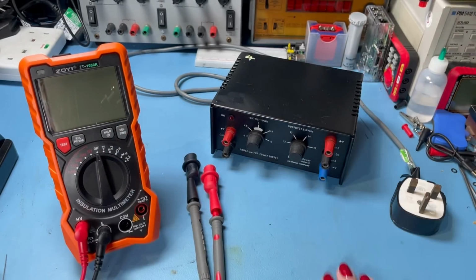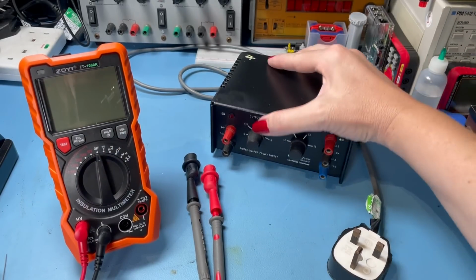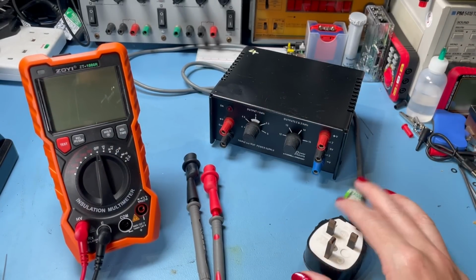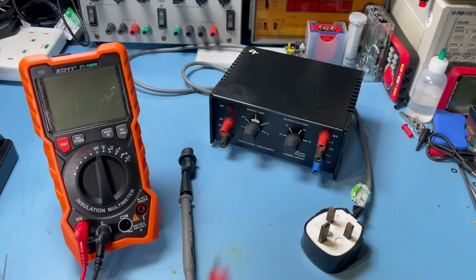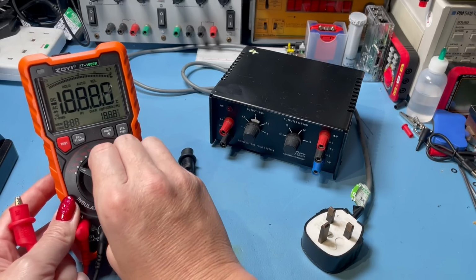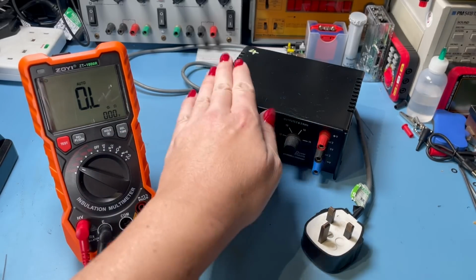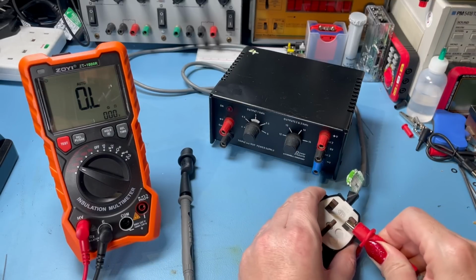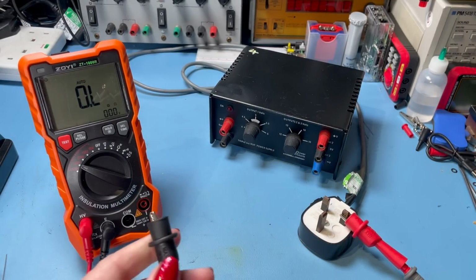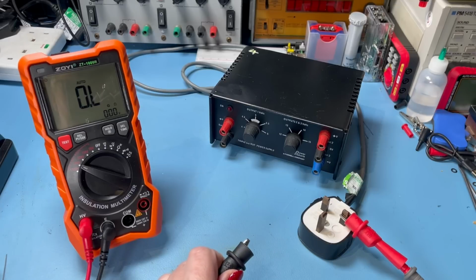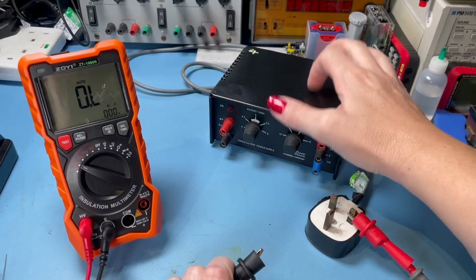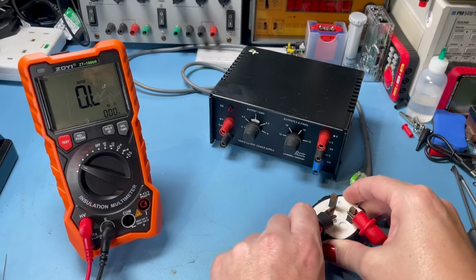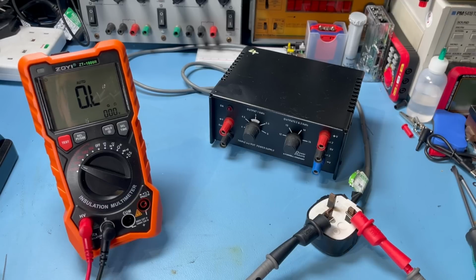Okay, so one final test I'm going to do with insulation testing then is this old power supply here. Now, I'm no stranger to testing appliances with my PAT tester, so let's have a look at this. We can do this at 500 volts because it's 250 volt rated, so we can do a test on insulation of the plug and lead, and then we'll do a test of insulation between the live and the casing of the appliance, which is generally what you do with the PAT tester. Now, I am just going by common sense and experience. There are probably other ways and other things you can do to test this.